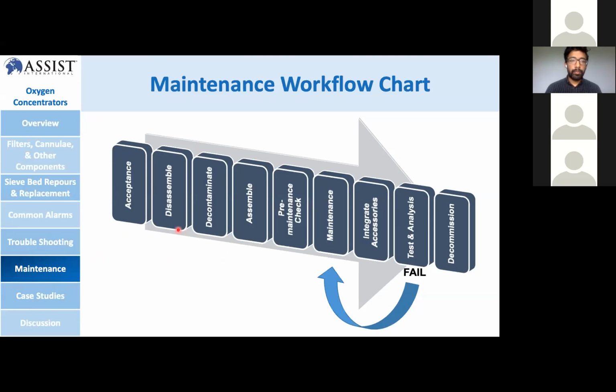any accessory and power cord on it. We remove the battery if it has any, and any mounted units, for example a humidifier on an oxygen concentrator or an EMS module on a monitor, we dismount it. And then we continue with the next process, which is decontamination. In the decontamination, I already have a slide coming up that would describe it very briefly. So I will go to the next process now, that is assembly. That is just putting everything back together. Everything that should be mounted, we put back in, the battery we put back in, and we plug in all the power cords and accessories.